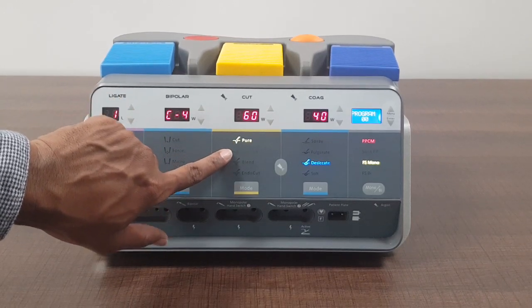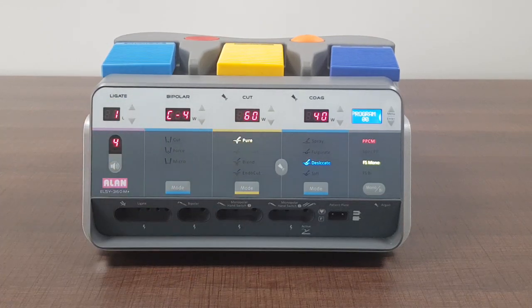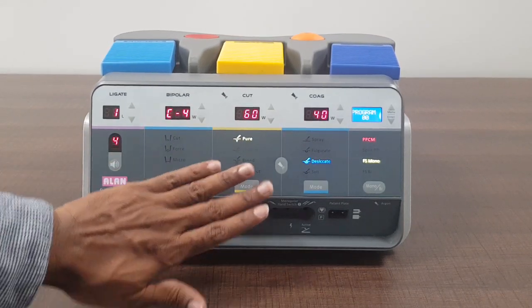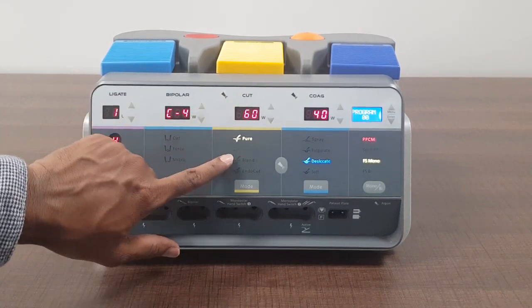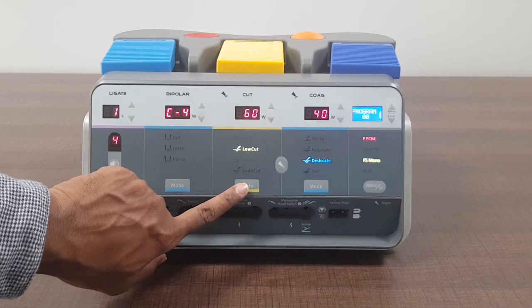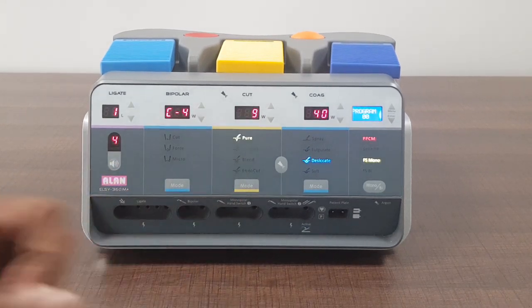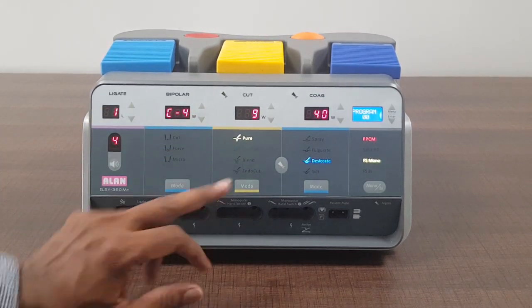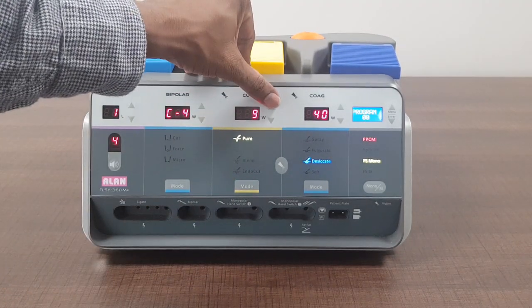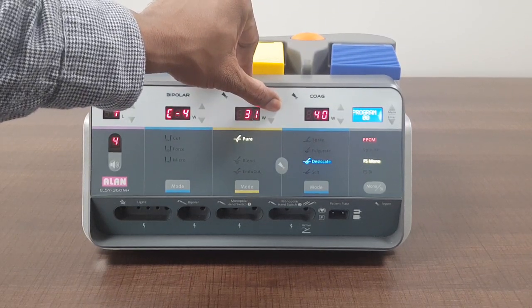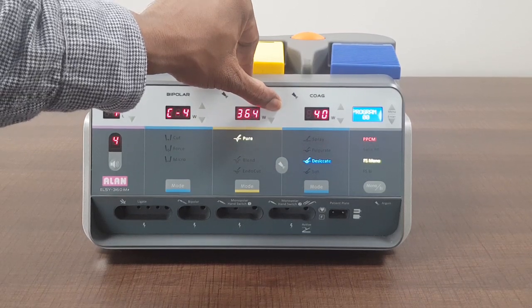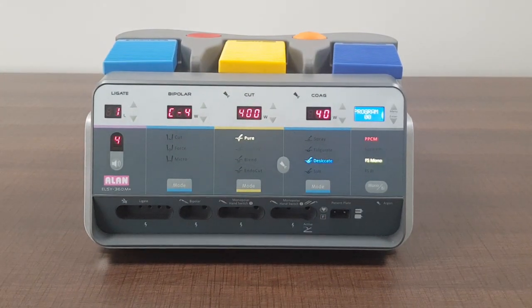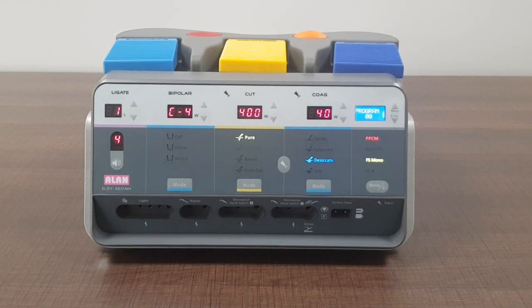Now if you can see the modes here: pure, low cut, blend, endo. I hope you will be able to see. You can check it on your machine over there. How to change modes? By pressing this option you see that it keeps changing like that. So in cut mode we have four modes. First one is pure cut which has the maximum of 400 watts. Pure cut is basically used for cutting just like any other machine.